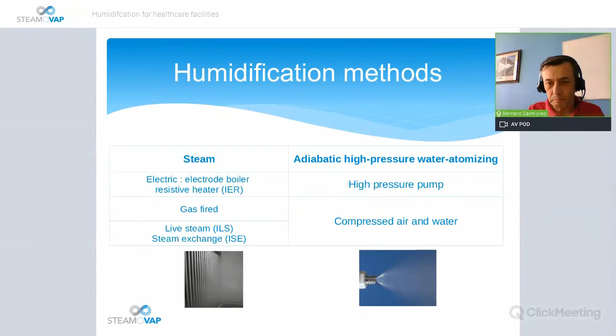So let's look at the steam, and we will compare the different equipment. Electrode boiler, the capacity range would be from 3 to 200 pounds. The good points are it's compact and easy to install, but the downside is the cost of operation and the waste. You remember the plastic bottle, you have to throw it away and replace it with a new one. You can use it for a small air handling unit or for point of use, so to humidify in a section of a space in the duct.